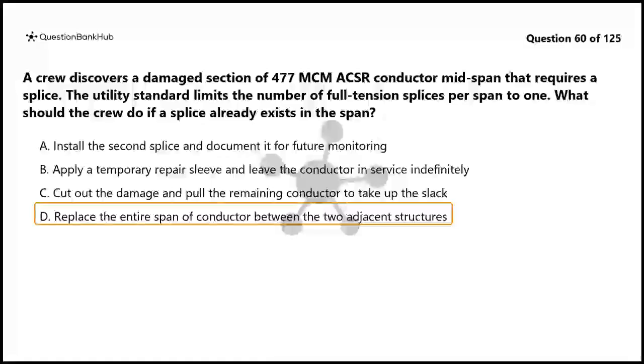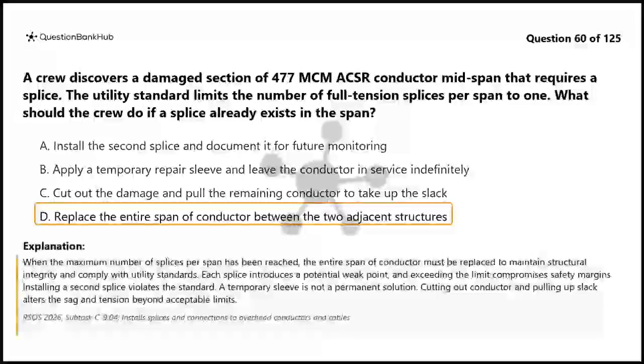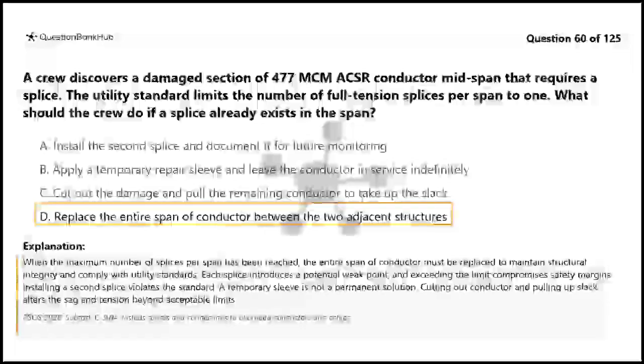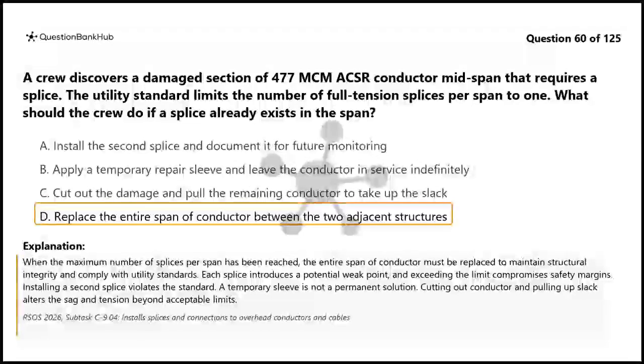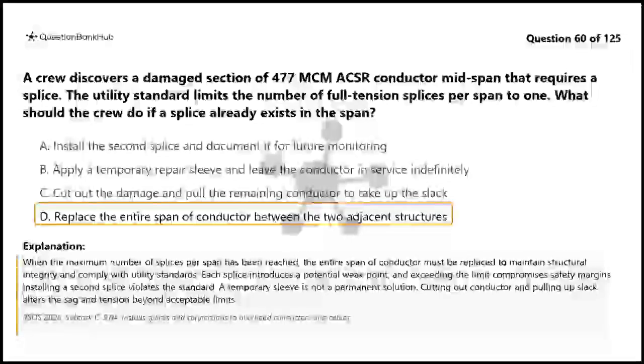The correct answer is D. When the maximum number of splices per span has been reached, the entire span of conductor must be replaced to maintain structural integrity and comply with utility standards. Each splice introduces a potential weak point, and exceeding the limit compromises safety margins. Installing a second splice violates the standard. A temporary sleeve is not a permanent solution. Cutting out conductor and pulling up slack alters the sag and tension beyond acceptable limits.